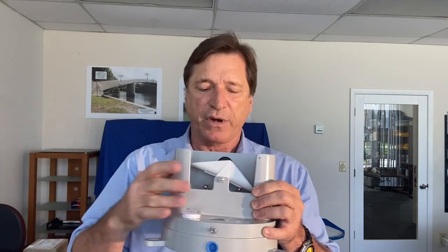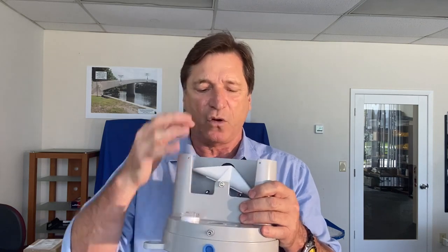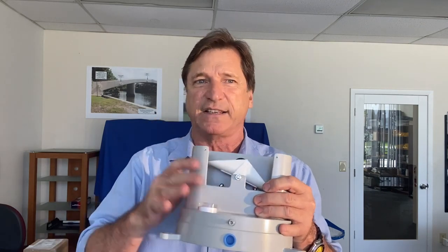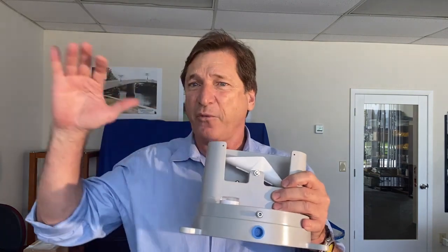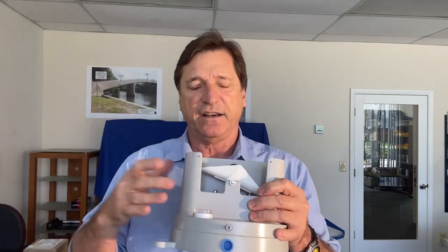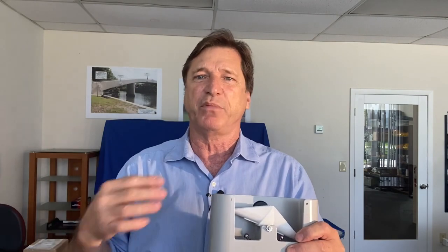Rather than go into an exceptional amount of detail, all this basically means that at low rates it's not that critical, but at higher rates, particularly now where we have so many cloud bursts and high intensity storm events around the world, as that intensity goes up, without a correction, the rainfall data will be significantly impacted by the underreporting of the gauge. So this correction mechanism that we've had for a very long time means that the TB3 and TB4...